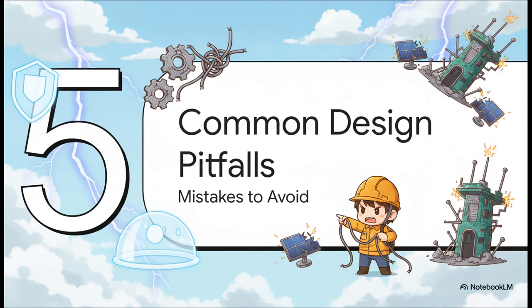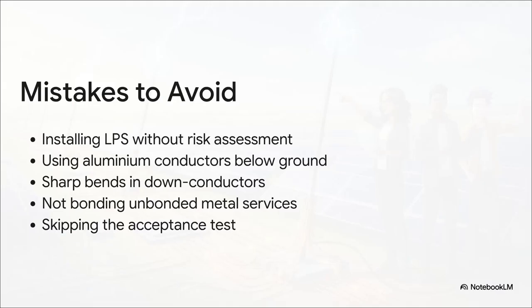Finally, Section 5, Common Design Pitfalls. Let's wrap up with the easiest ways to fail your system design in the real world. Pay really close attention here so you don't repeat these field mistakes. Number 1, installing an LPS without doing the risk calculation first. Seriously, don't waste the client's money if R1 doesn't demand it. Number 2, and this is absolutely critical, never bury aluminum conductors underground. Aluminum reacts violently with soil and corrodes so fast. Always use copper below grade.